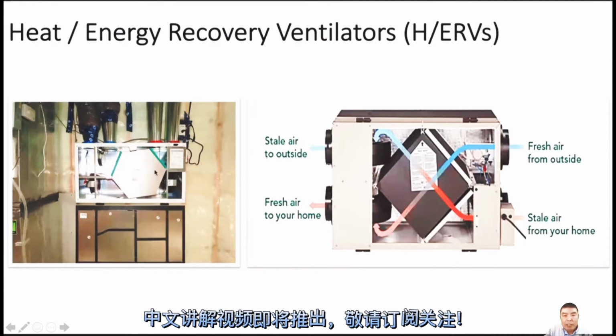For the HRV and the ERV, the big difference is this heat exchanger. Normally in Canada, what we see is mostly the HRV. I only saw the ERV in commercial buildings. I never saw a residential ERV here in Canada, because our climate is good for the HRV. An ERV is normally used in areas close to the sea or with very high moisture in the summertime. Those areas may use the ERV more than the HRV.